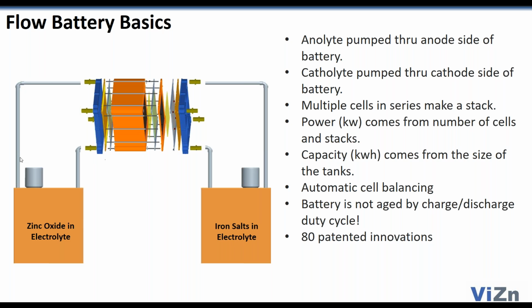Key thing in flow battery stacks in any large battery array is cell balancing. Our system has built-in electronic controls which rebalance cells to each other in real time while the system's running, and that minimizes maintenance and maximizes the stability of the system's capacity, so you do not see the degrading that occurs in systems because of cell-to-cell imbalance.